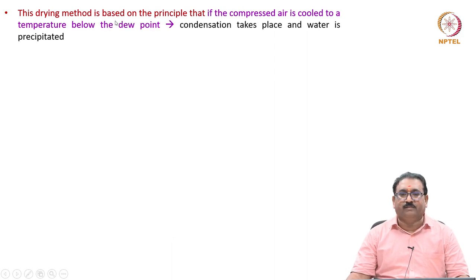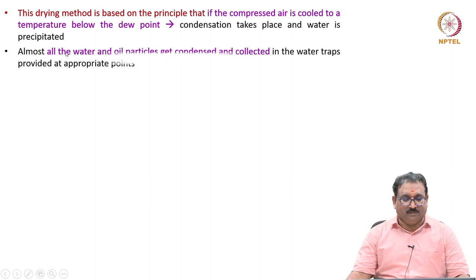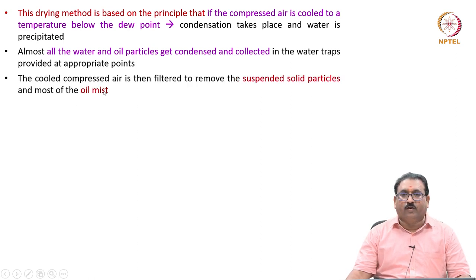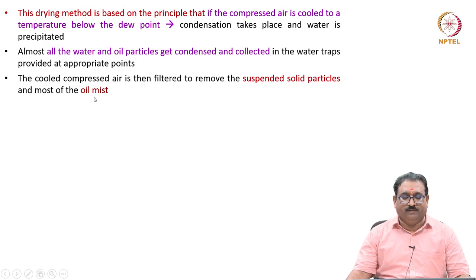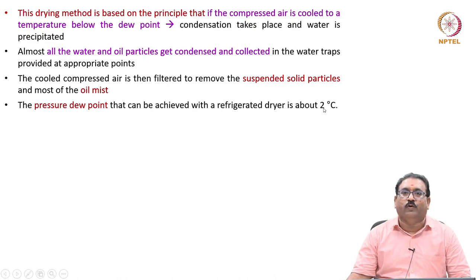This drying method is based on the principle that if the compressed air is cooled to a temperature below the dew point, condensation takes place and water is precipitated. Almost all the water and oil particles get condensed and collected in the water traps provided at appropriate points. The cooled compressed air is then filtered to remove suspended solid particles and most of the oil mist. The pressure dew point that can be achieved with the refrigerated air dryer is about 2 degrees centigrade.